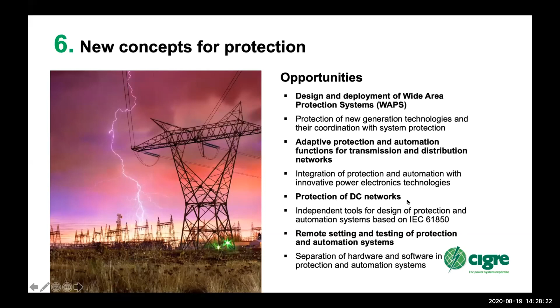With DC, the issue is that you need to detect and trip within about 2 milliseconds, whereas with AC systems you can use a cycle or even more than that on MV networks. So this is really an area that needs further work — then there's remote setting and testing of protection and automation systems.